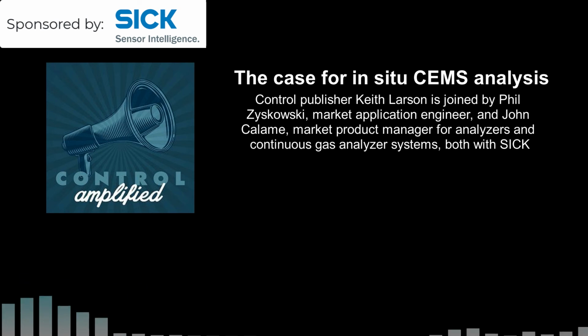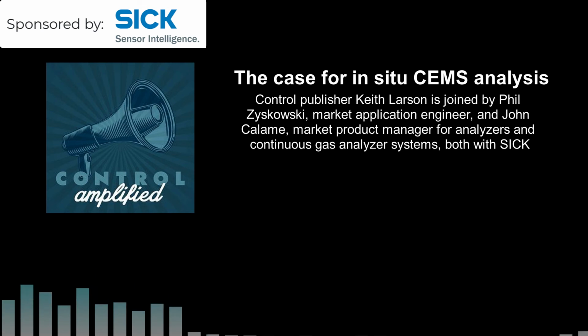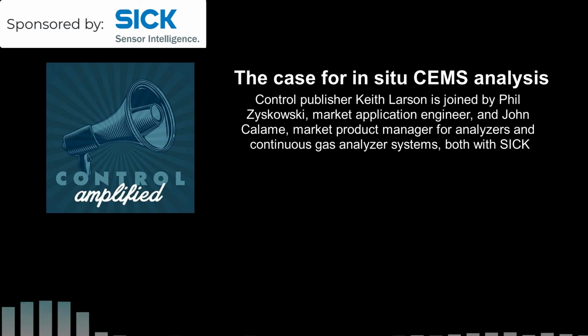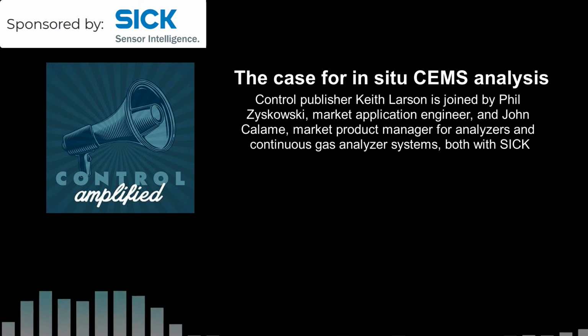When you move into chemical, petrochemical, and refining industry spaces, there are different regulations and different hazardous area electrical requirements, usually a minimum of Class 1, FM Class 1 Div 2, or in some instances Class 1 Div 1. From a supplier standpoint, we have to comply with the electrical area classification. It's trickier, but we have solutions for Class 1 Div 2, either in a purged enclosure or a non-incendive type arrangement to be safe in those areas.